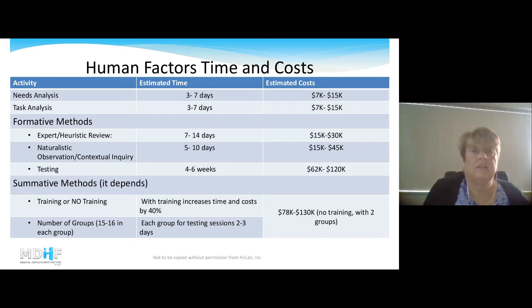Surgical devices are sometimes more difficult because you'll have to either use a wet lab, a simulated environment that may not meet the stress of what the actual environment would be, or you have to do it in conjunction with a clinical trial. My caution to you is if you're doing things in conjunction with a clinical trial, in terms of the FDA, you need to get permission from the FDA to do your human factors testing in parallel. In other words, I'm not talking about the preclinical human factors testing. I'm talking about concurrent, okay? But it can be done. They just want to know that that's what you're doing, okay?